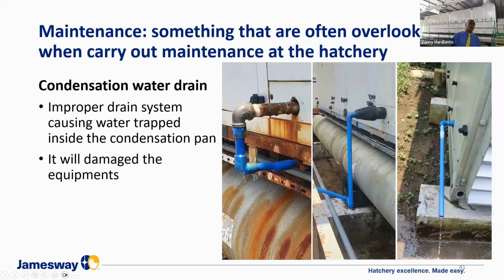We continue with the condensation water drain, especially in the air handling unit. When I do customer visits, a lot of them do not pay attention to this. Improper drain pipe will cause water to be trapped inside the pan. So when the trapped water goes to unwanted areas inside the unit, it can damage everything.